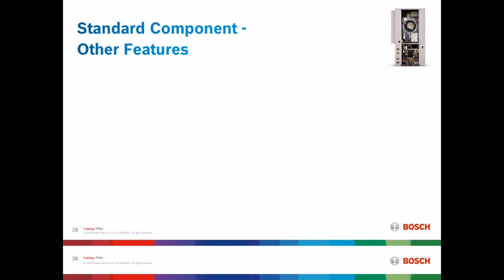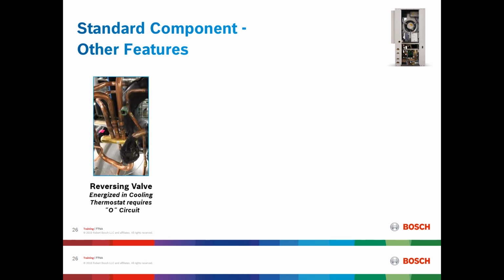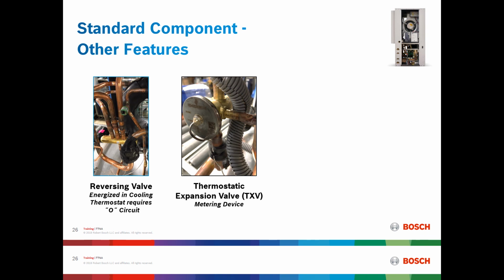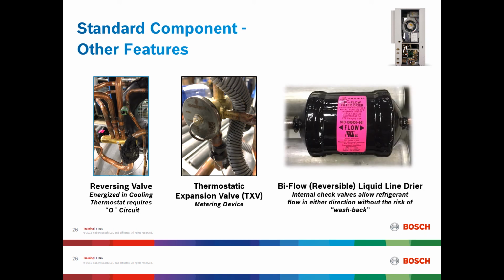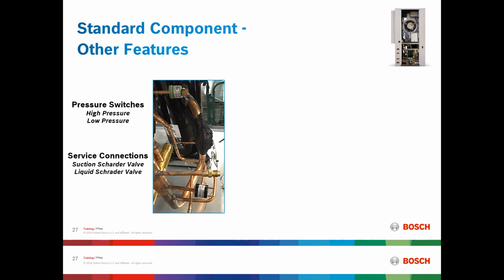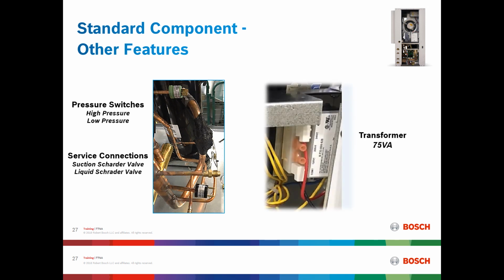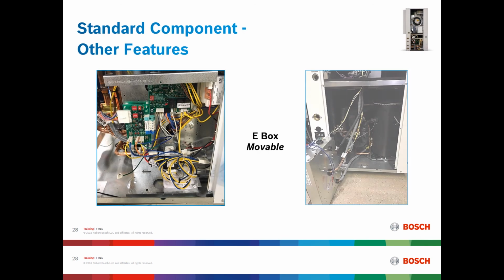Other standard features in the SM-Rev-V model include a reversing valve that is energized and cooling. Therefore, the thermostat will require the O circuit. The machine has a thermostatic expansion valve or TXV metering device, as well as a bi-flow reversible liquid line dryer. This dryer comes with internal check valves that allow refrigerant flow in either direction without the risk of any washback to the compressor. Other features will include pressure switches, a high pressure switch and a low pressure switch, service connectors within the unit, one for suction and one for liquid, as well as a 75 VA transformer. Another standard feature will be the E-box, which is movable and can be rotated out to access internal components of the unit.